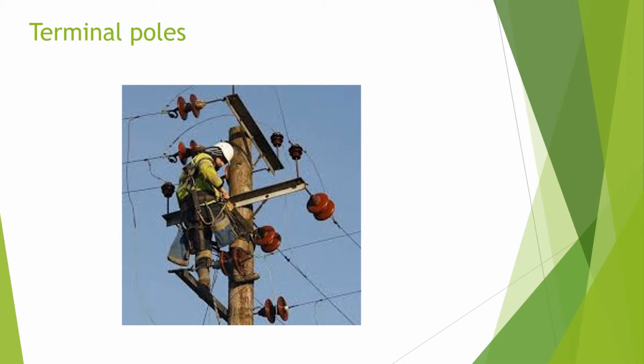These crossarms are also utilised where there is a requirement to spur a section of line off the main line. The terminal crossarm supporting the end of the spur conductors would be mounted below the crossarm supporting the main line, and the two sets of conductors linked by jumpers. Two sets of terminal crossarms are often used instead of a section pole crossarm if the angle of the turn required is too great for a section crossarm.